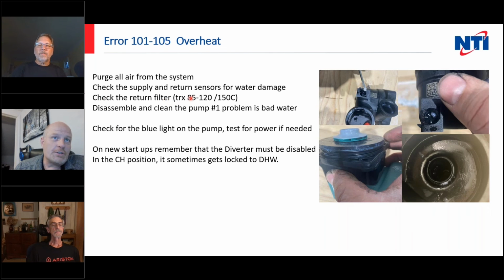Check the return filter on the TRX 85 to 120 and the 150 combi. It's built into the boiler. It often gets plugged with debris if you've got a water quality issue. Disassemble and clean the pump. This is the #1 problem for this error code. So you take the pump out, you pull this impeller out, clean the magnet, clean the rotor, make sure there's no junk in there. Check for the blue pump light on, make sure you've got power to the pump and, if you don't have power, diagnose why that would be.